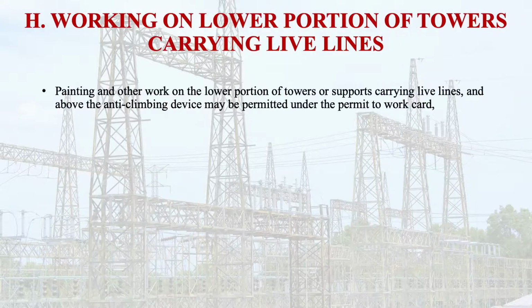So painting and other work on the lower portion of the towers or supports carrying live lines and above the anti-climbing device may be permitted under the permit to work card, provided that suitable precautions are taken to ensure that all persons carrying out the work are acquainted with the distinctive marks, that means the caution order, that have been placed on the tower and the support.